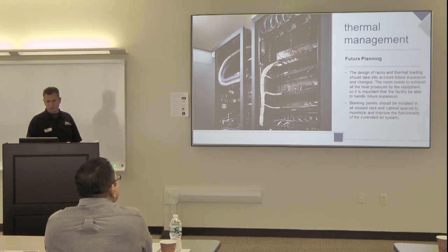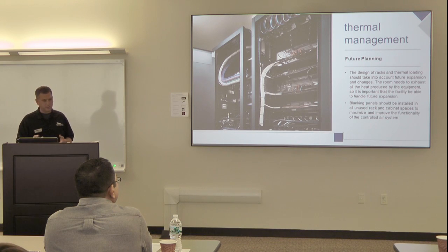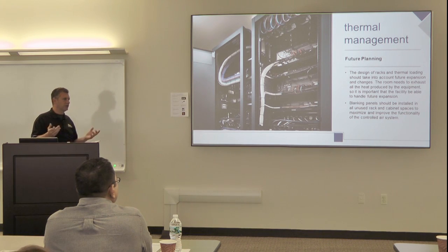And then basically, again, we talked about future planning, the design of the racks, the thermal load. You want to know what that is, the type of room that it is. Blank panels are always good to have around. Again, if you think you're going to have some empty rack spaces for future stuff, put a blank panel in there. You want to keep that air from coming in and out of there.